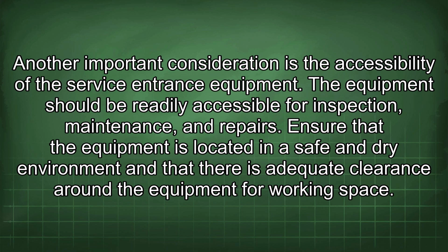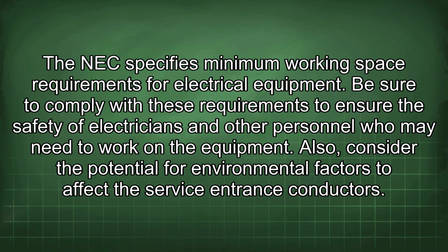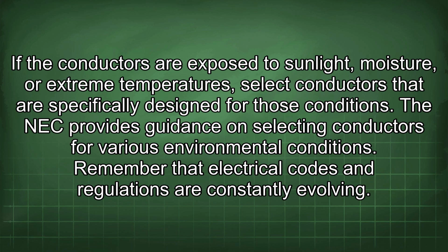Another important consideration is the accessibility of the service entrance equipment. The equipment should be readily accessible for inspection, maintenance, and repairs. Ensure that the equipment is located in a safe and dry environment and that there is adequate clearance around the equipment for working space. The NEC specifies minimum working space requirements for electrical equipment. Be sure to comply with these requirements to ensure the safety of electricians and other personnel who may need to work on the equipment. Also, consider the potential for environmental factors to affect the service entrance conductors. If the conductors are exposed to sunlight, moisture, or extreme temperatures, select conductors that are specifically designed for those conditions. The NEC provides guidance on selecting conductors for various environmental conditions.